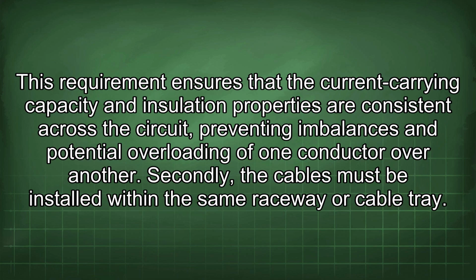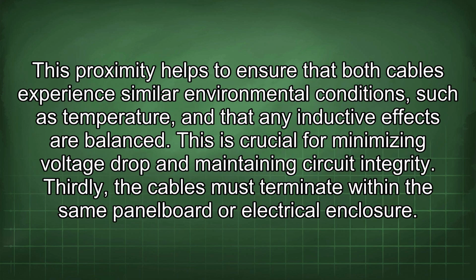Secondly, the cables must be installed within the same raceway or cable tray. This proximity helps to ensure that both cables experience similar environmental conditions, such as temperature, and that any inductive effects are balanced. This is crucial for minimizing voltage drop and maintaining circuit integrity.